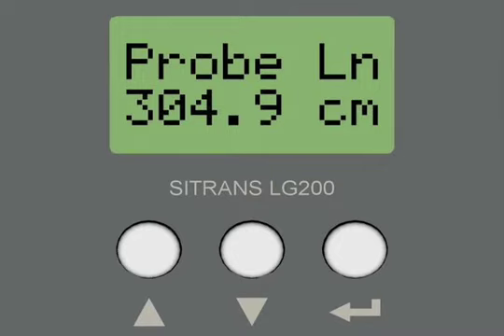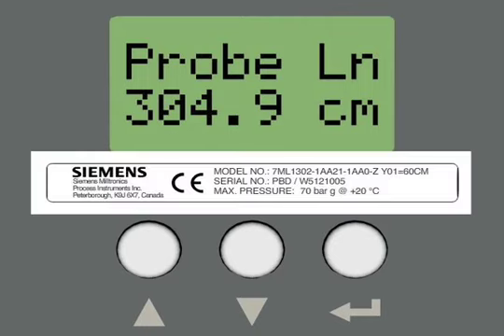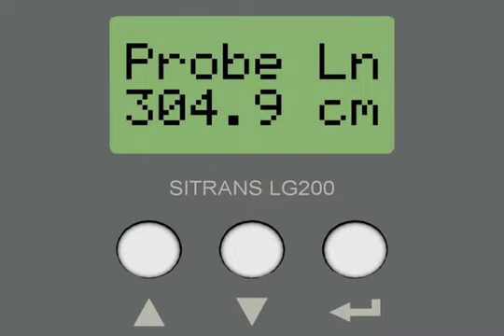The probe length needs to be input into this parameter. The length of the probe is listed on the probe nameplate. This length is always given in centimeters and is the last digits of the model number. Our probe has a length of 60 centimeters. To enter this value in the probe length parameter, we push the Enter key to activate edit mode. When we push the up or down arrow key once, the displayed value will change by 1 millimeter. When we push and hold the up or down arrow key, the displayed value will change by increments of 1 millimeter at first, and then change by increments of 1 centimeter, and finally change by increments of 10 centimeters.